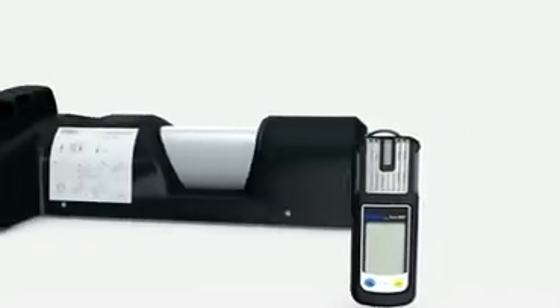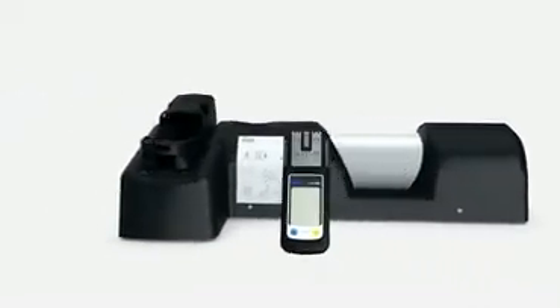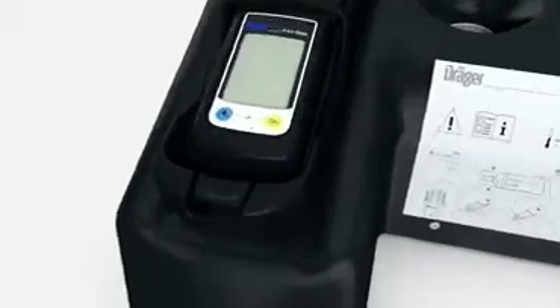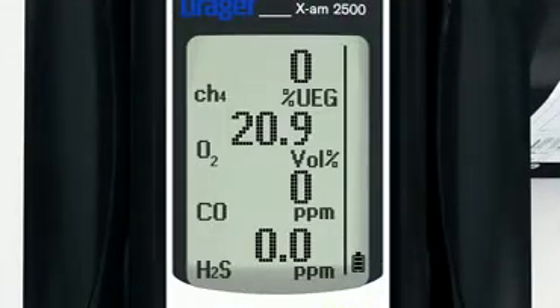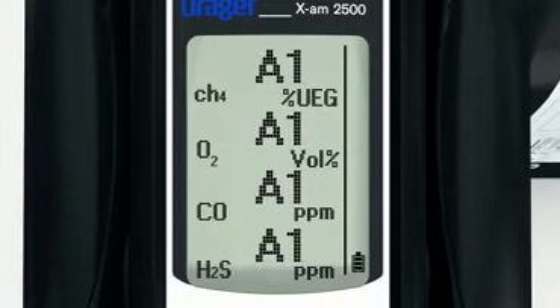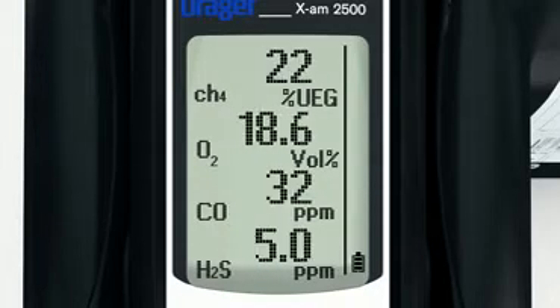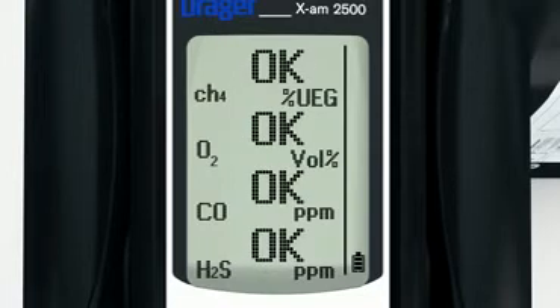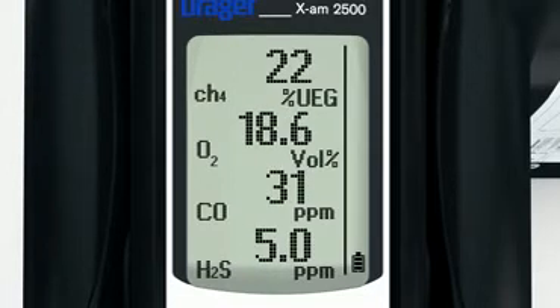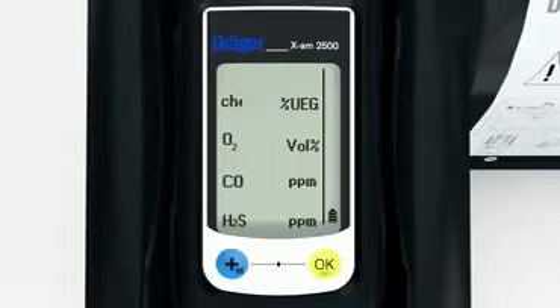Place the switched-on instrument inside the calibration cradle, where it will be recognized automatically. Gas now flows automatically over the sensors and the alarms are shown. If the bump test passes, OK will flash in the display to show that the bump test is now complete. If a functional test does not take place correctly, a channel error is shown for the sensor or sensors. The device will have to be calibrated and possibly repaired.